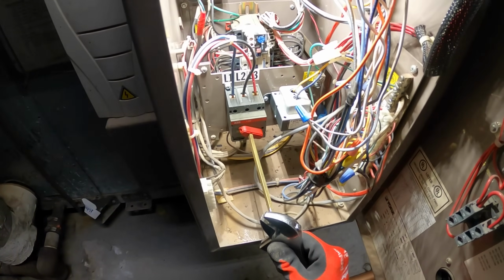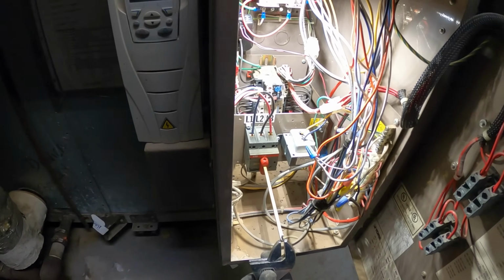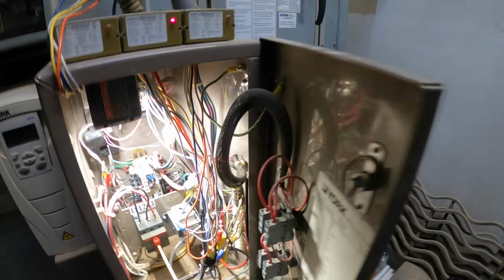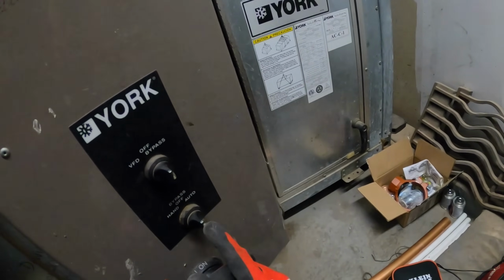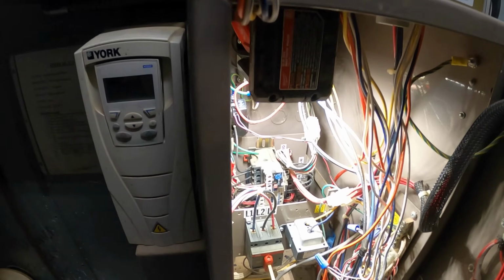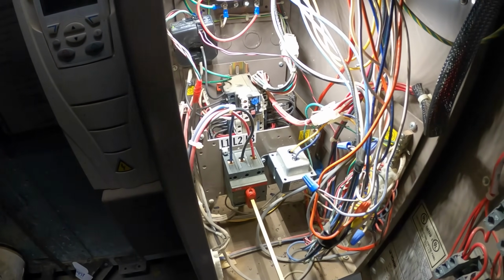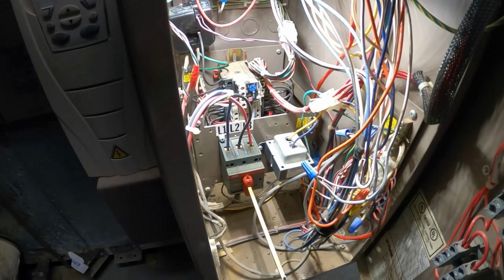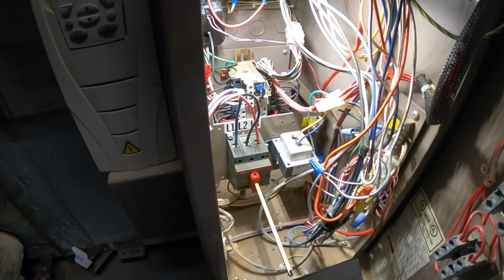All right, if we turn this on, there should be power. But the thing is, what do we have it set to? All right, off at the moment. So VFD, let's bypass that. I want to see, does the contactor plunge in? Excuse me, the motor starter. A motor starter is basically a large contactor with an overload.